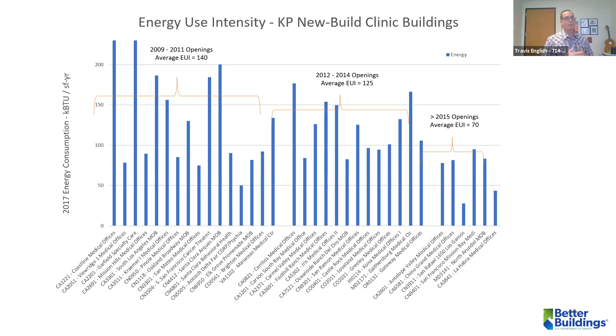Our energy target was 50 EUI - that's what our energy model showed. The models actually pretty consistently show lower than that, but actual consumption comes in higher, significantly and consistently higher. There's a name for this: the energy performance gap - the gap between what our calculations say will happen with energy and what really happens. In most of our designs, that gap is somewhere between 50% to 100%. Pretty significant.